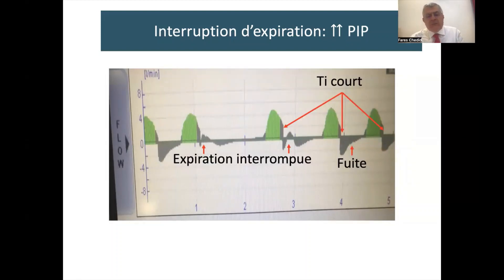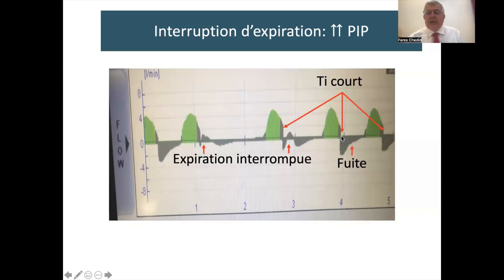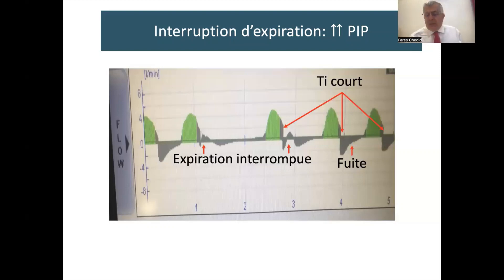Here is a patient of mine showing interrupted expiration: the patient started expiring, then inspired, then expired again. That small partial expired volume is incorrectly treated as the total expired volume, and the next breath's PIP shoots up. At the same time, we see inspired flow area larger than expired flow area due to leak — but that's handled by leak compensation. We also see a short inspiratory time in this tracing, which I'll address in a few slides. The key message: interrupted expiration can falsely increase PIP.